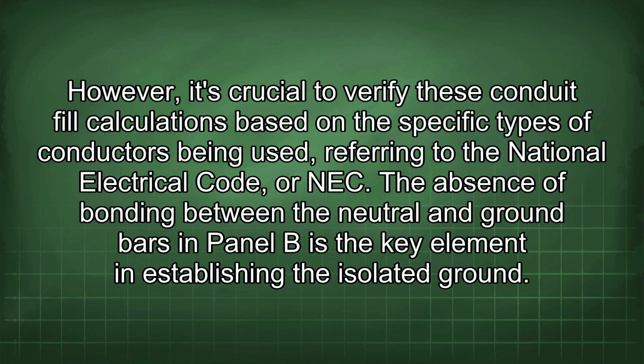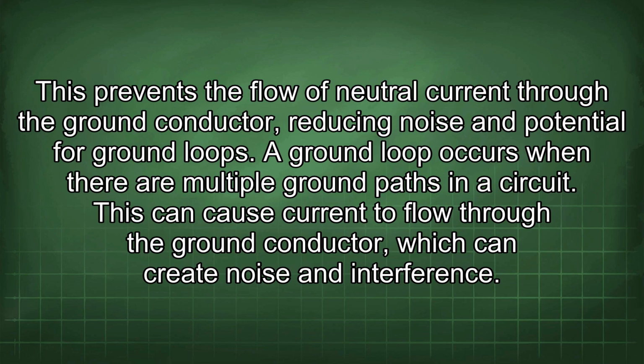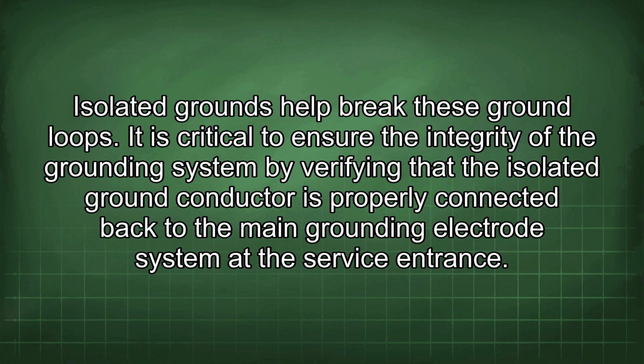The absence of bonding between the neutral and ground bars in panel B is the key element in establishing the isolated ground. This prevents the flow of neutral current through the ground conductor, reducing noise and potential for ground loops. A ground loop occurs when there are multiple ground paths in a circuit. This can cause currents to flow through the ground conductor, which can create noise and interference. Isolated grounds help break these ground loops.